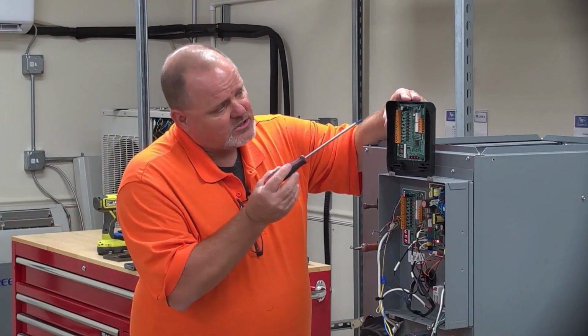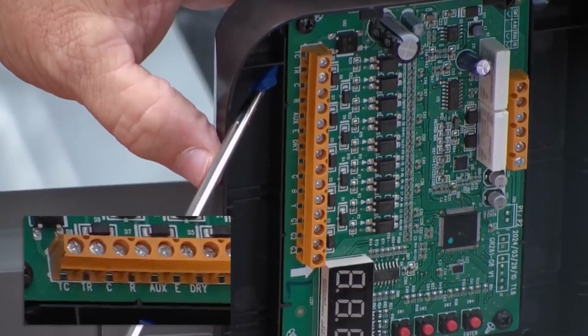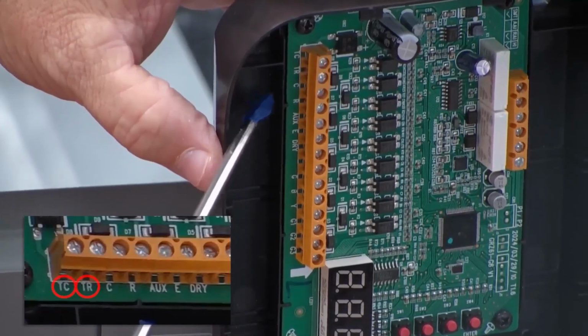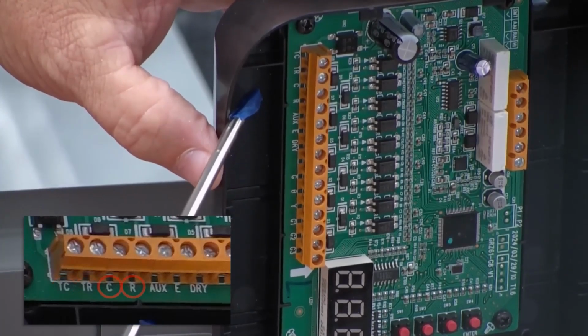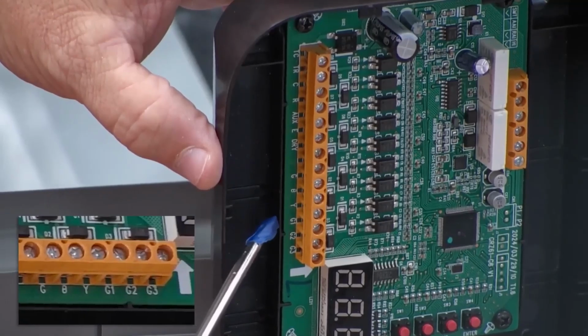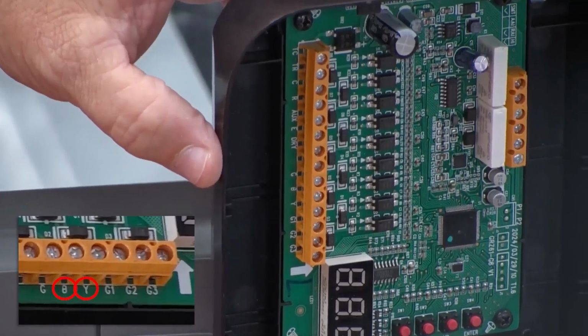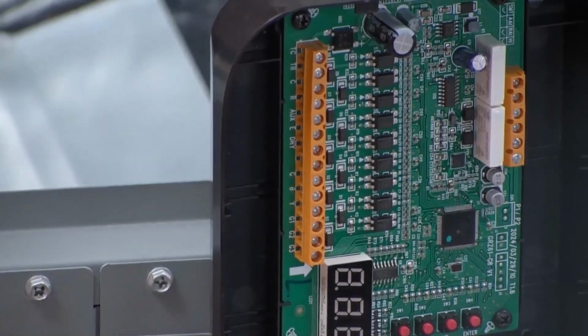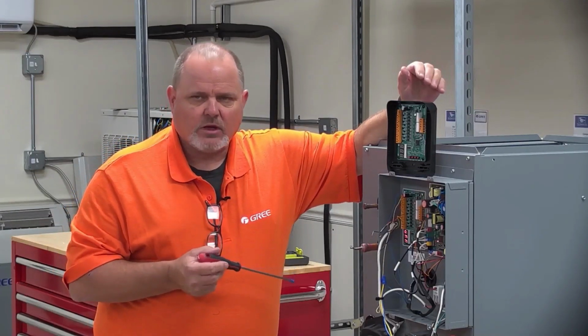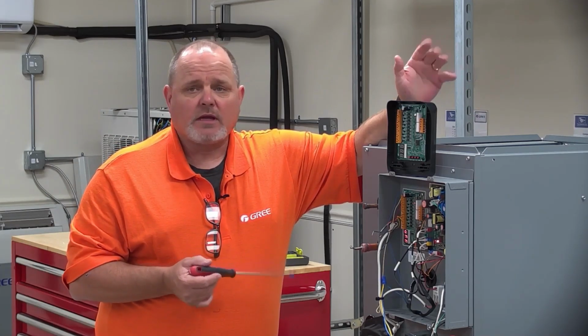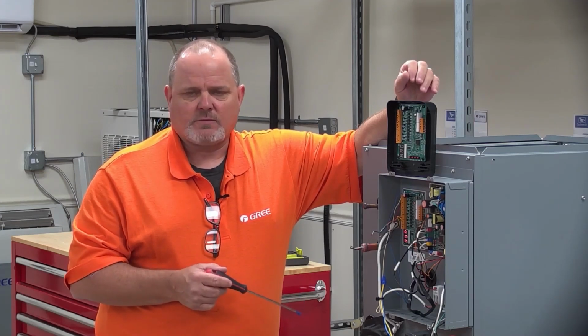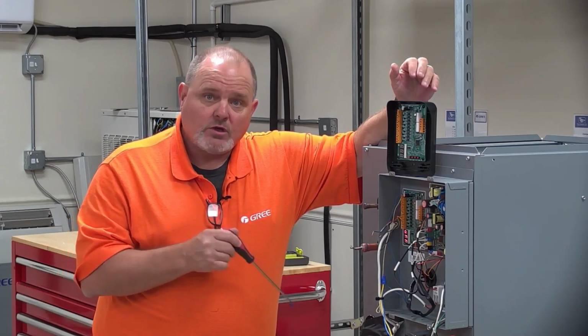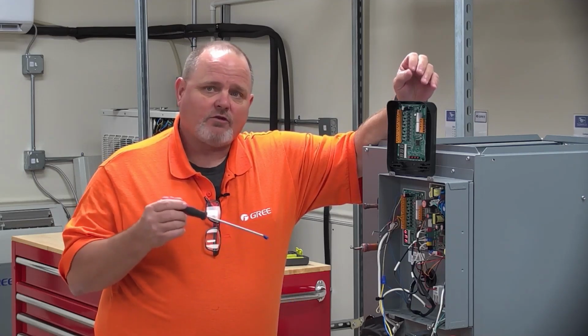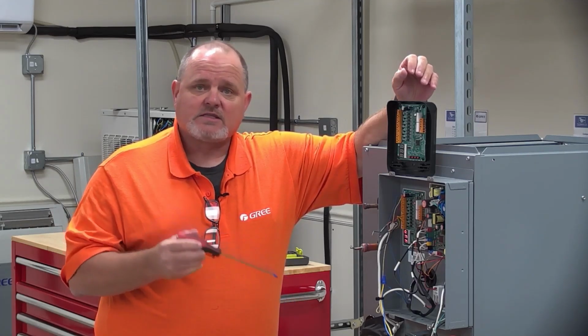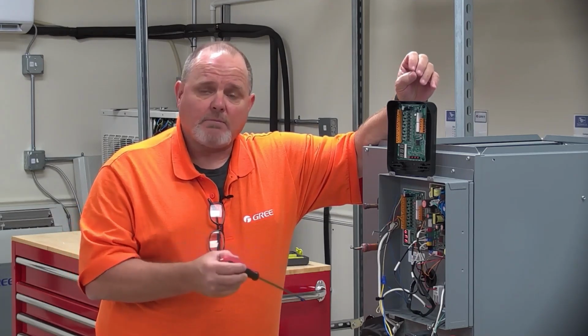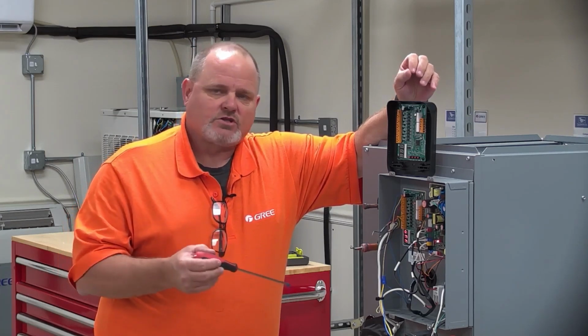So the only connections, again, just to refer: you're going to put your 24 volts from your furnace at TC and TR. You're going to have your C and your R going out to your thermostat. And then you're going to have your Y and your B. You don't need to hook up G or dry or auxiliary or W1, because your auxiliary heat is going to be your gas furnace. Now, keep in mind, since we're doing dual fuel, you have to have a dual fuel capable thermostat that is not going to send out a signal and try to run the heat pump and the gas furnace at the same time.